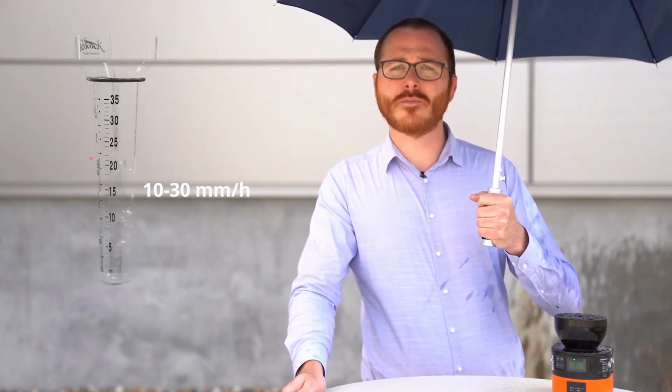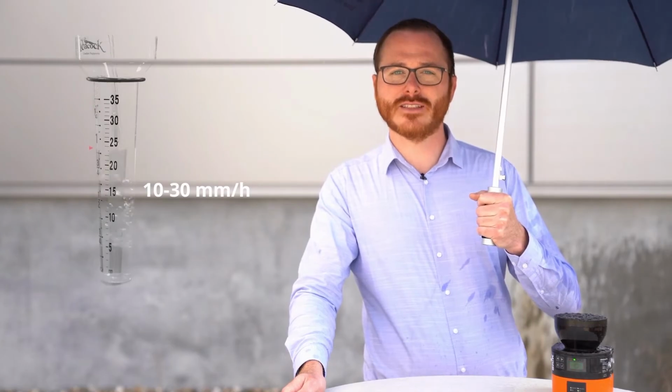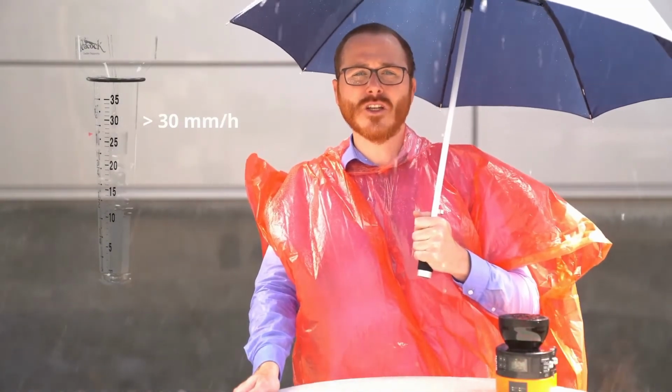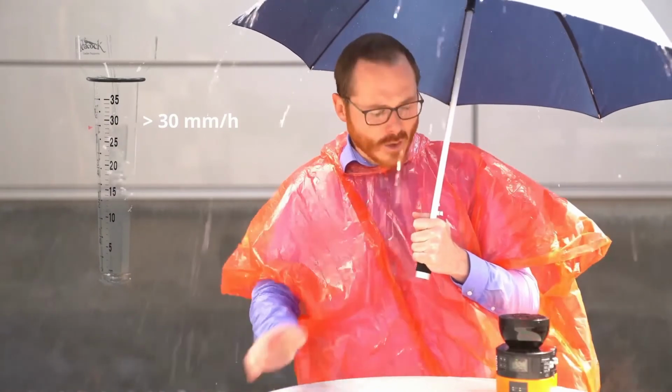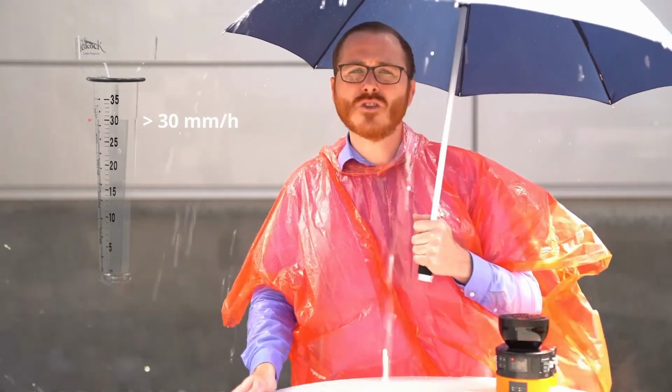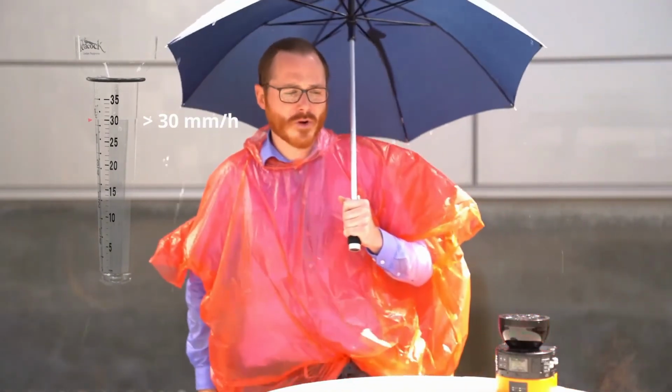But there will be some sporadic infringements of the protective field. The third scenario is very heavy rain. This type of rain usually lasts only several minutes. The outdoorScan3 will now change into a safe stop condition. As soon as the rain will stop, the outdoorScan3 will start normal operation again.